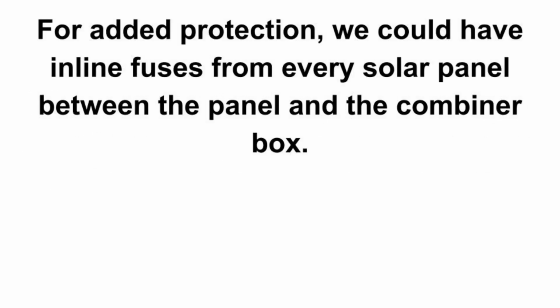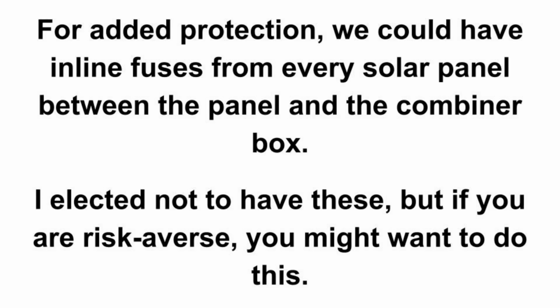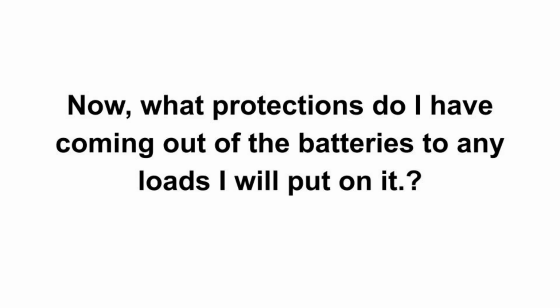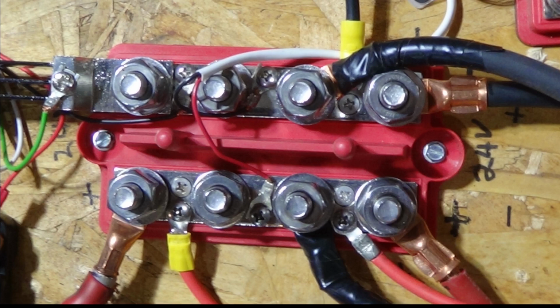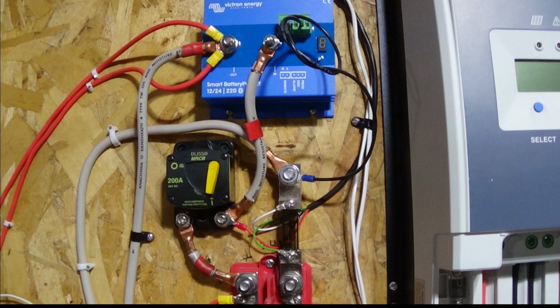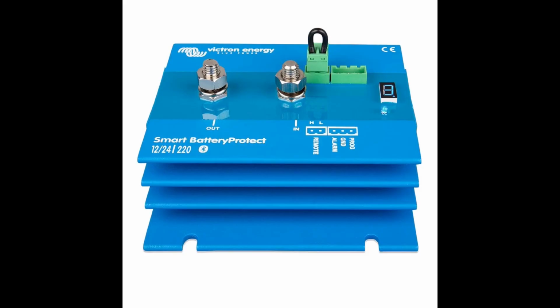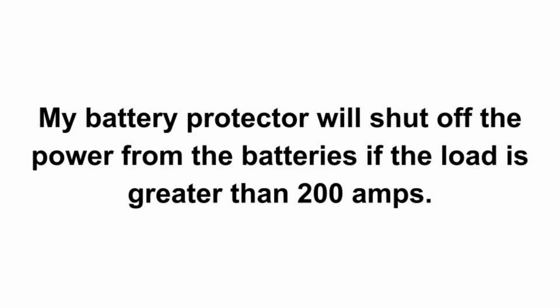For added protection, we could have inline fuses from every solar panel between the panel and the combiner box. I elected not to have these, but if you are risk-averse, you might want to do this. Now, what protections do I have coming out of the batteries to any loads I will put on it? Between the bus bars of the parallel connected batteries and any loads, I have a battery protector. This electronic protection will monitor the amount of load being used from the batteries. My battery protector will shut off the power from the batteries if the load is greater than 200 amps.